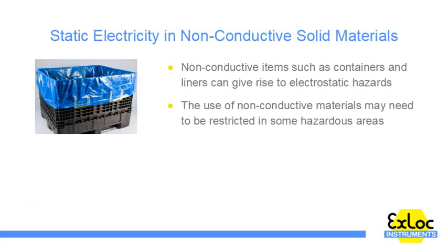Static electricity in non-conductive solid materials. Non-conductive solid materials are being used increasingly in equipment and structures in many forms, including pipes, containers, coatings and liners, and their use in hazardous areas can give rise to electrostatic hazards. These include the possibility of a conductive section of plant becoming isolated from earth by its non-conductive seals or flanges, allowing it to become charged and give rise to sparks.